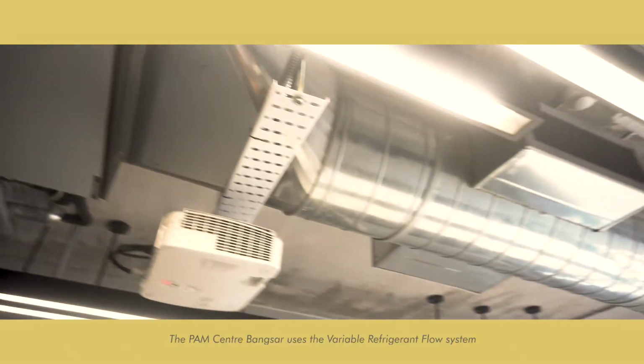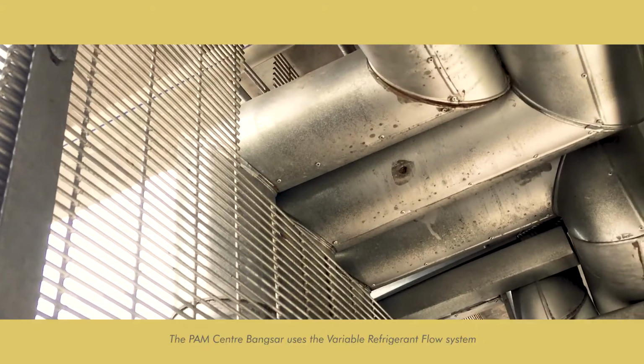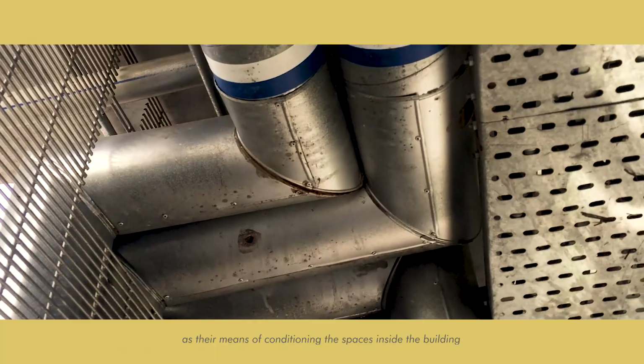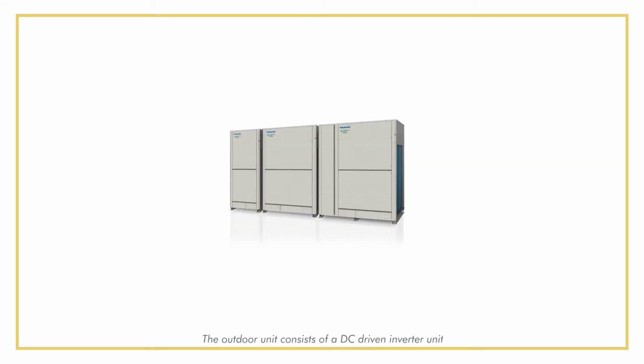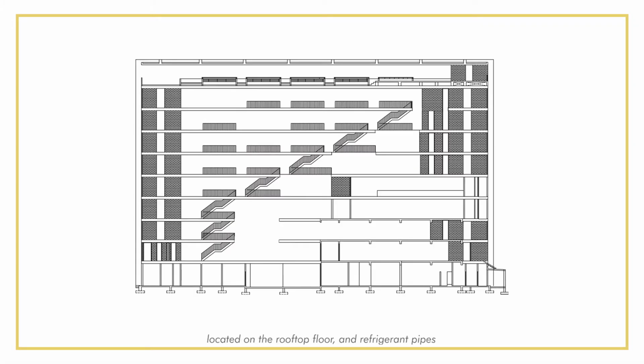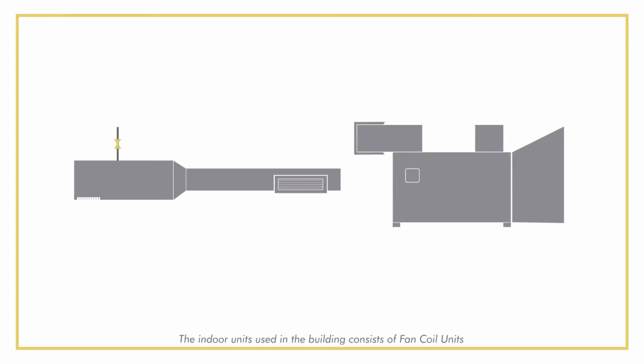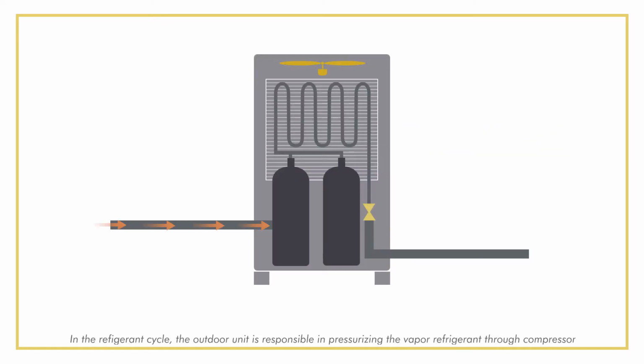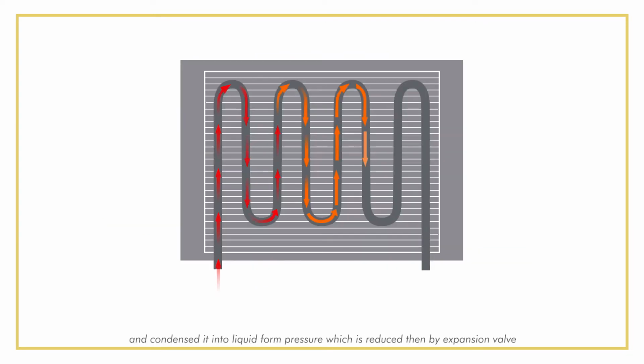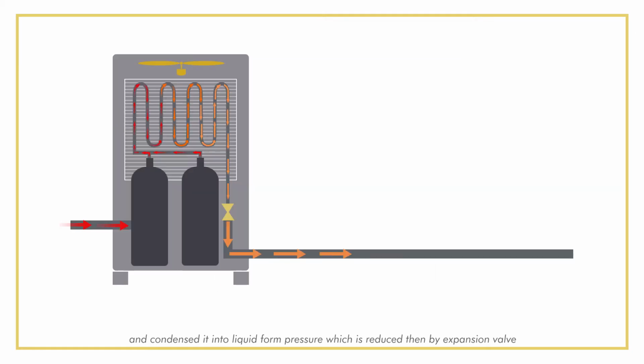The PAM Center Bangsar uses the variable refrigerant flow system as its means of conditioning the spaces inside the building. The outdoor unit consists of a DC driven inverter unit located on the rooftop floor and refrigerant pipes. The indoor units used in the building consist of fan coil units as well as the air handling unit that houses evaporating coils. In the refrigerant cycle, the outdoor unit is responsible for pressurizing the vapor refrigerant through the compressor and condensing it into liquid form, whose pressure is then reduced by the expansion valve.